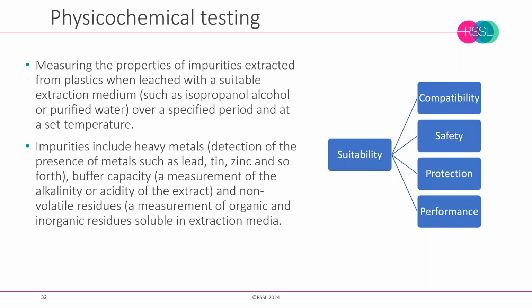So we're trying to measure the likelihood of impurities that can be extracted from plastics when they're leached using our extraction medium. So not only are we going to be using product, we also might need to replicate that with something like isopropyl alcohol or purified water over a specified period at a set temperature. And then we'd be measuring for a whole range of impurities. So this could be heavy metals like lead, zinc, tin, and so on. It could be an alteration to acid or alkalinity. It could be the release of organic or inorganic residues. So there's all sorts of things that can come out.